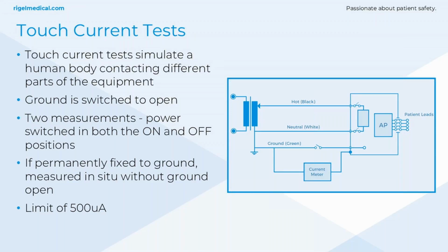So with this type of test, you're looking at any current that's going to flow to a person from the equipment chassis or any part of the equipment that's not intended for patient treatment or care, so applied parts. This is applied to all portable equipment, and unlike IEC 60601, there are no single fault conditions except the ground is open. So you've got to make sure that the ground switch is open, and I'll show you how that's done in the touch current test.